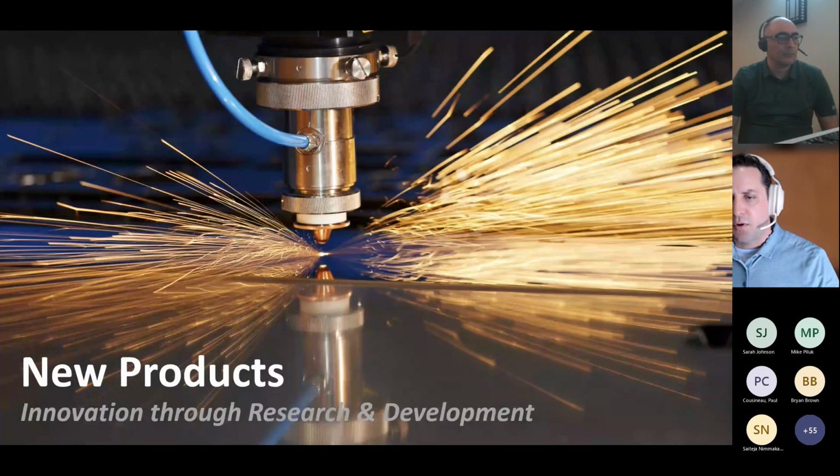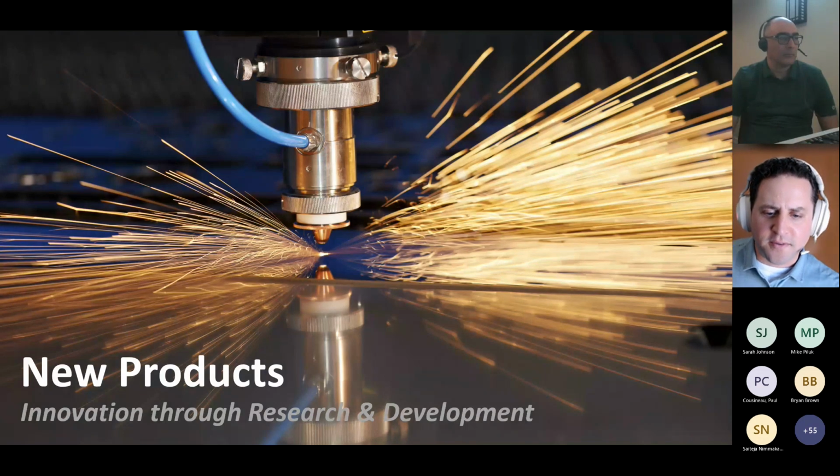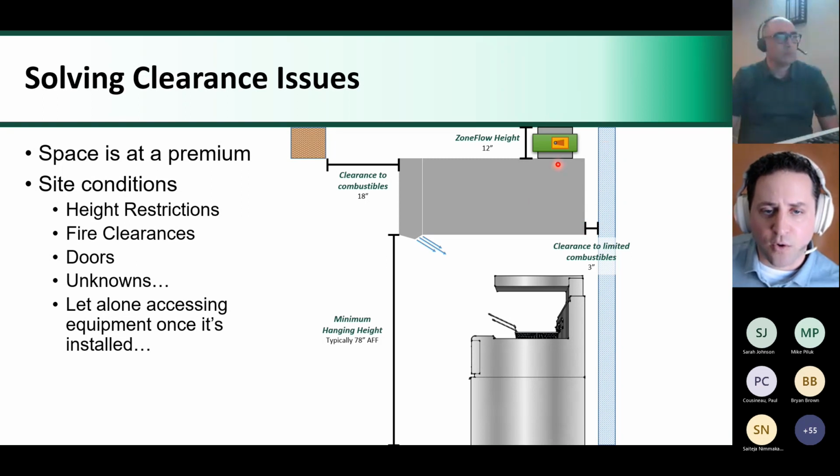So for us, new products, we like to try and do new things. Actually, we have some people at Spring Air who, I swear, refuse to do anything on existing equipment and only like to think of new ideas, which is great. So we're always playing in the lab, trying to come up with something new. These two things that we talk about really solve clearance issues for us. If you look at traditional hoods, you've got a clearance to combustibles of 3 inches. If you've got modulating or manual balancing dampers, that's about 12 inches required on top of the hood, plus just clearance to combustibles.